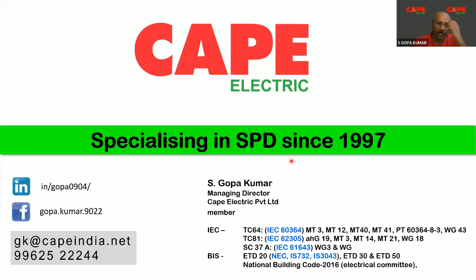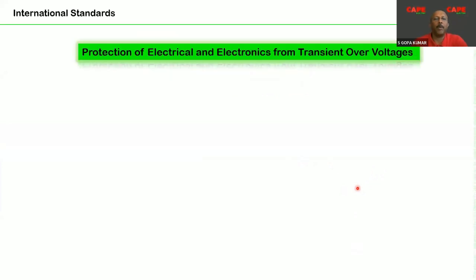At that time, industry didn't know what an SPD is. I'm talking about 97 or 98. So we installed our first SPD for an industry. Of course, before that we were doing it for wind turbines, but that was our first experience. And finally, we could solve the problem. The customer was so happy, and nobody expected that an SPD is so efficient in stopping the tripping of a variable frequency drive.